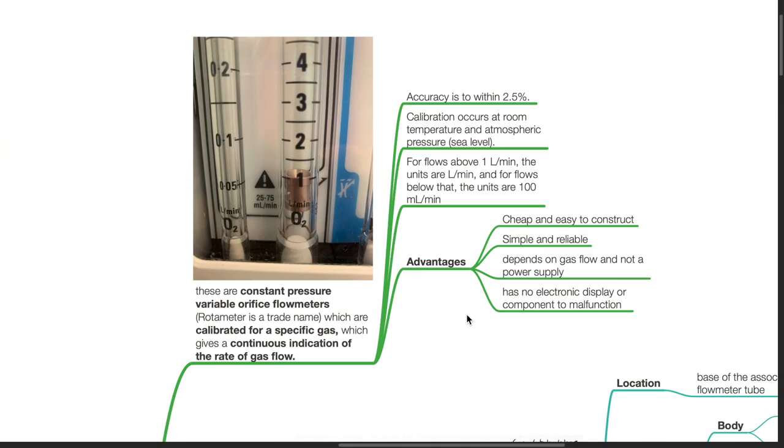These are constant pressure variable orifice flow meters which are calibrated for a specific gas, which gives a continuous indication of the rate of gas flow.